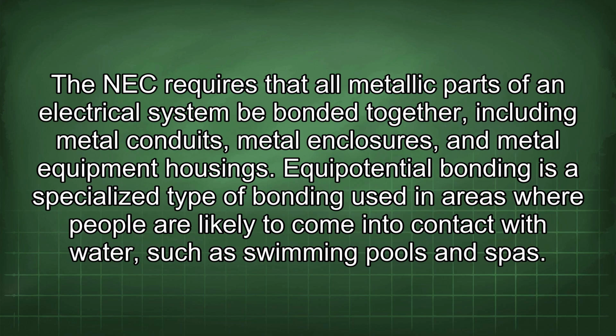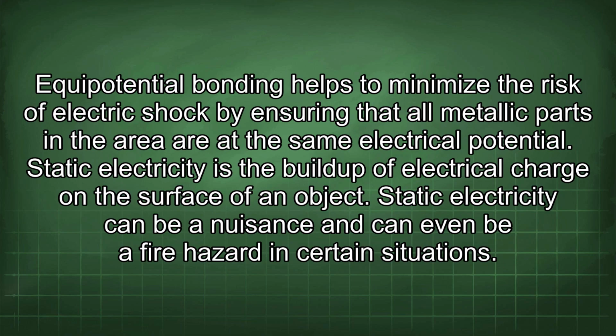The NEC requires that all metallic parts of an electrical system be bonded together, including metal conduits, metal enclosures, and metal equipment housings. Equipotential bonding is a specialized type of bonding used in areas where people are likely to come into contact with water, such as swimming pools and spas. Equipotential bonding helps to minimize the risk of electric shock by ensuring that all metallic parts in the area are at the same electrical potential.